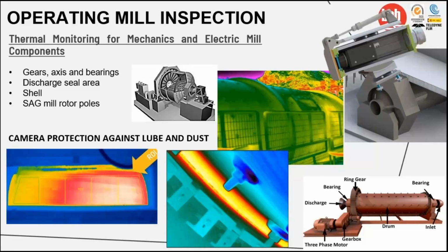In addition to this, we also inspect the liner seal, both at the inlet and outlet, by placing a camera that inspects this seal, checking the temperature it shows. As we can see in the image below, we precisely monitor the temperature along the mill liner and detect any thermal wear. This inspection is possible with a single camera and software. Well, what does the software do? The software analyzes these images and makes a scanning of the area so we can see all the 360 degrees.